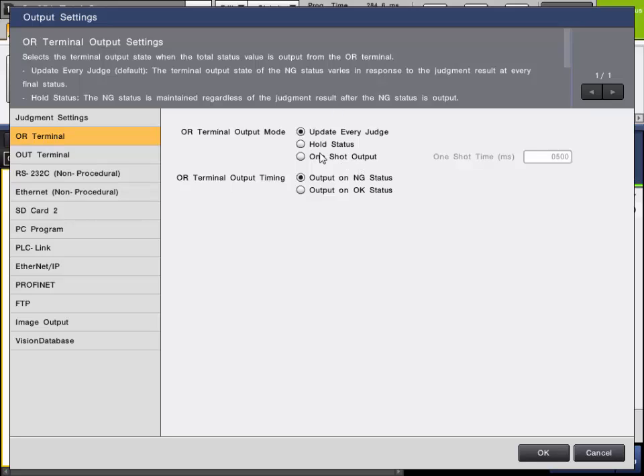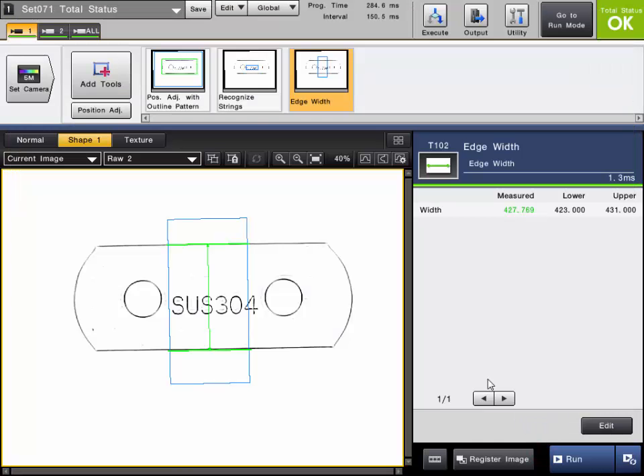We'll cover each one of these as an example. You can also dictate whether the output turns on for a no good status or on for an OK status. As a default, the OR is going to update every judgment — so every time you trigger, it will update. And as a default, it will output on no good status. The OR output or any of the other judgment outputs only operate while you're in run mode, so when testing this out, you need to be in run mode.